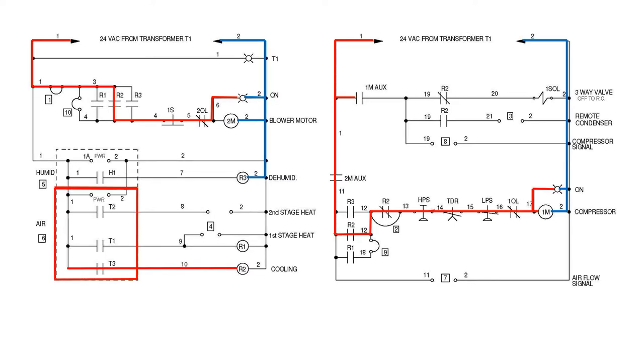One of these, a second pole on the R2 relay, can now provide power to the compressor circuit, which includes a time delay relay. Note, that if no external condenser is used, this jumper wire must be removed to prevent the compressor from starting in the cooling mode.